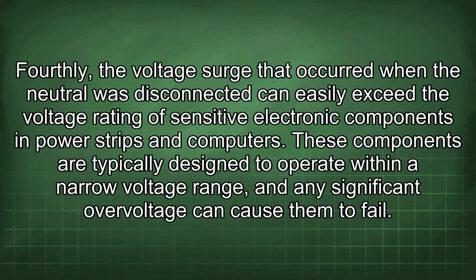Fourthly, the voltage surge that occurred when the neutral was disconnected can easily exceed the voltage rating of sensitive electronic components in power strips and computers. These components are typically designed to operate within a narrow voltage range, and any significant overvoltage can cause them to fail.